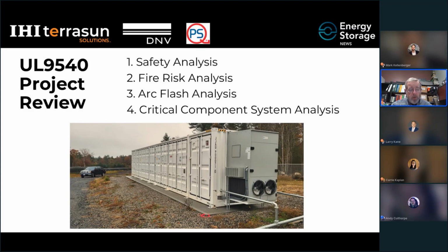While we're doing this, we also review the single line diagram, all of the components that are involved with the energy storage system, and the equipment layout. We look at clearances within the energy storage system, the cabling that's used and that it's appropriate for the application, overcurrent protection that's provided or that is needed, the temperature controls and verification that they are working, the fire protection that would be required, and the grounding and bonding requirements that are all part of 9540. And then of course the testing that would be required as well. The picture that you see there is a 4 megawatt hour energy storage system vessel.